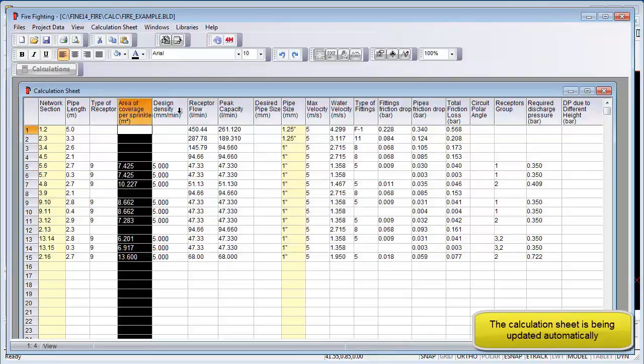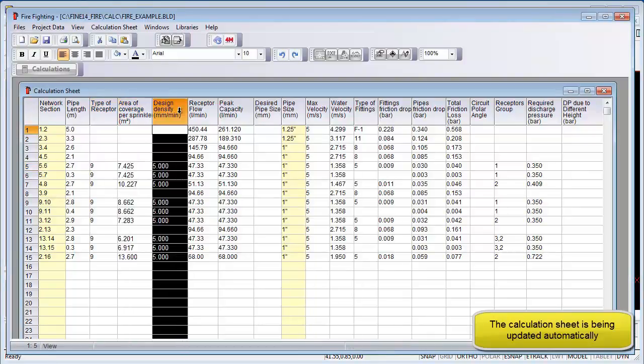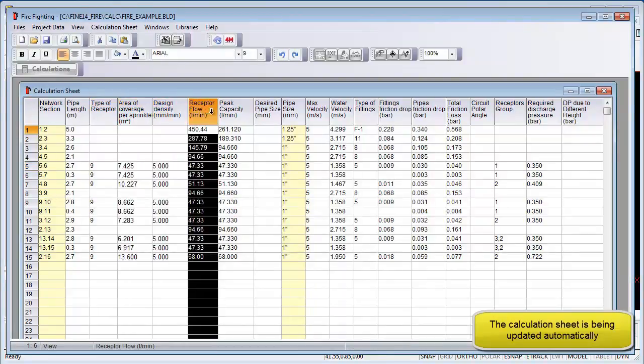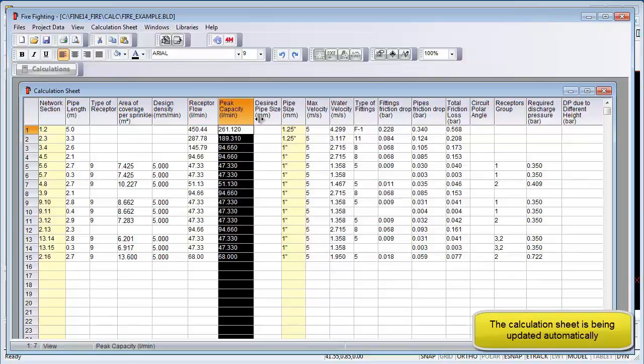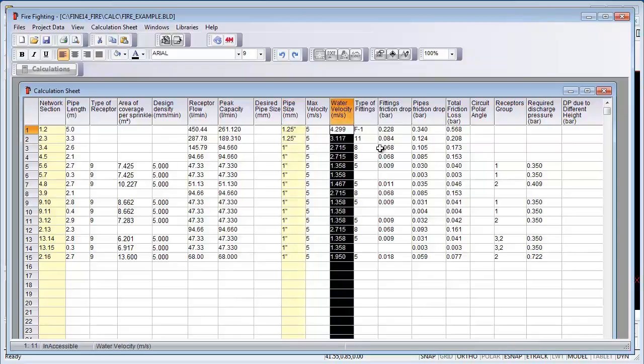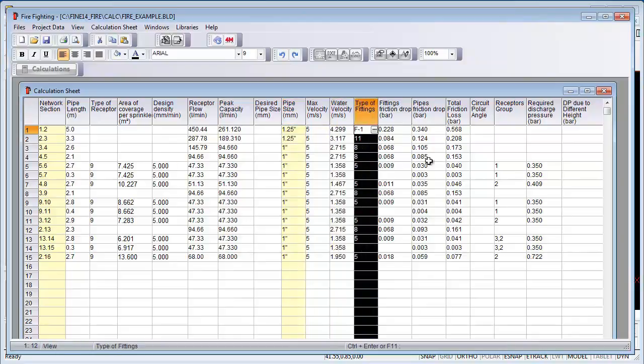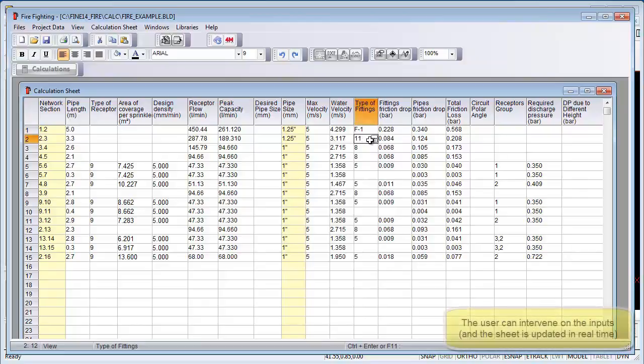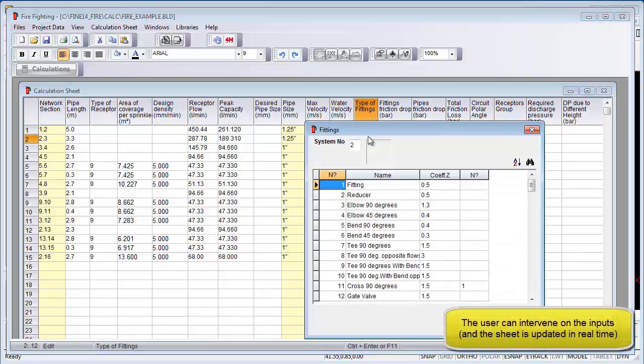Here are some of the results: the area of coverage, the density, the flow rate, the peak capacity, pipe size, and the velocity in the pipes. Here we are clicking onto the type of fittings — bends, etc. — so friction loss from bends. You can change those if you are not happy with them from the program.